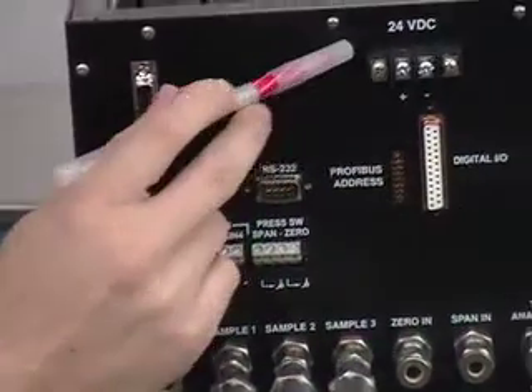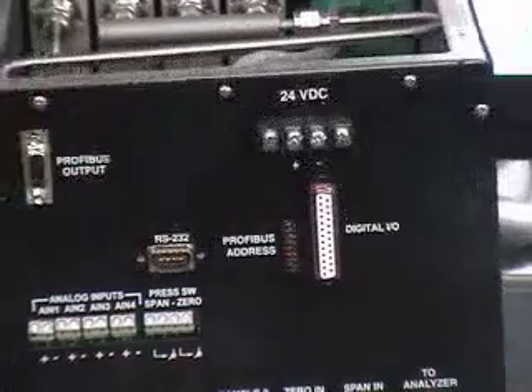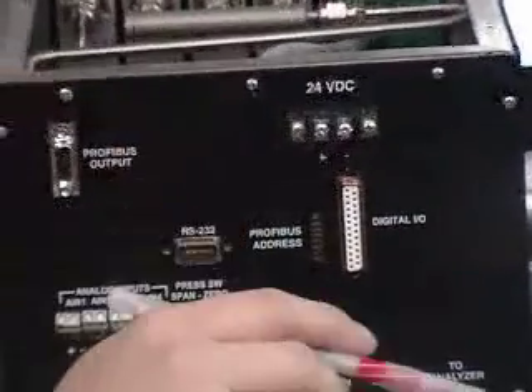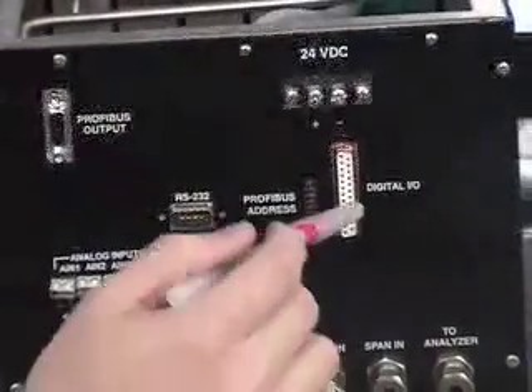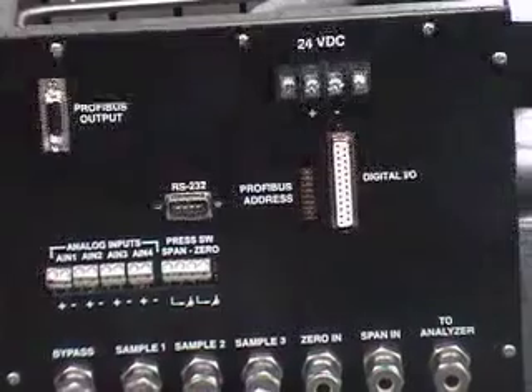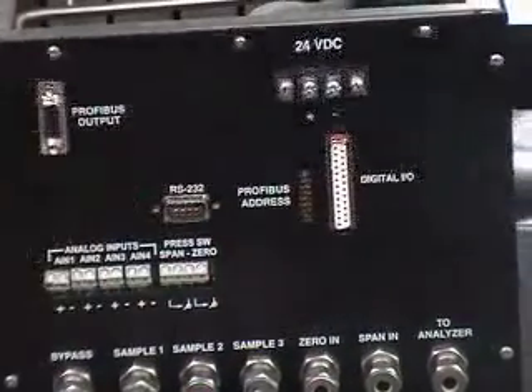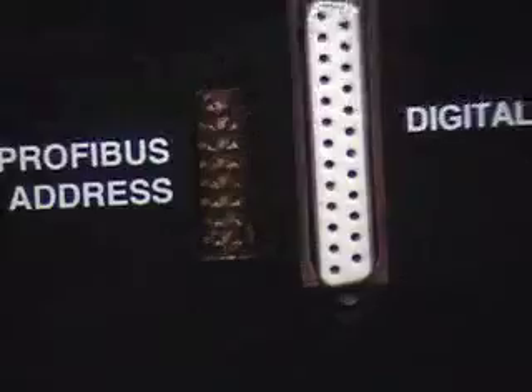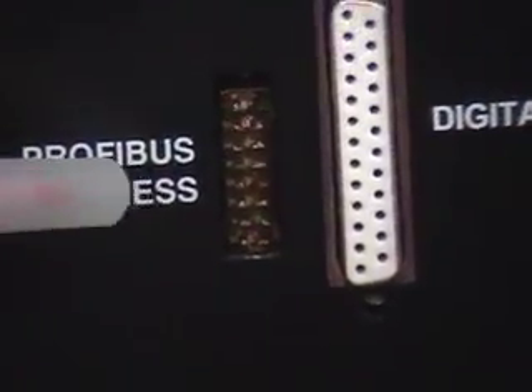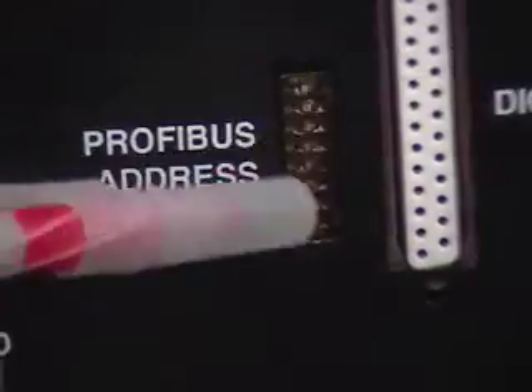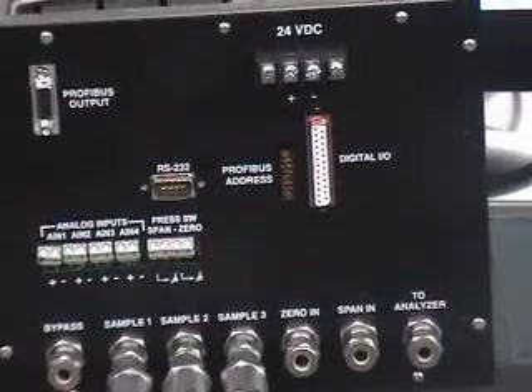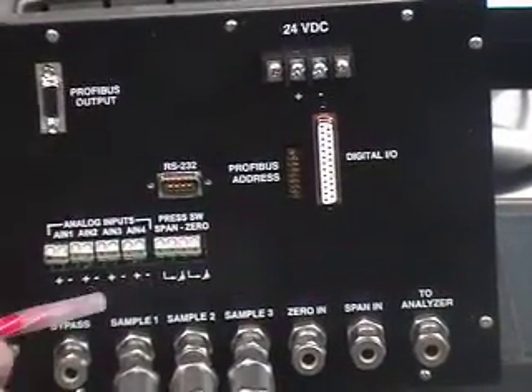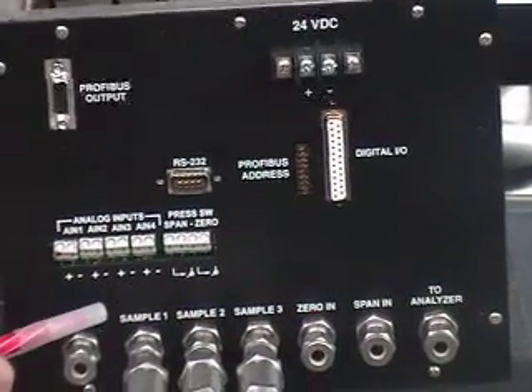This BB1 needs a 24-volt power supply, which we connect over here on this terminal strip. Now, to set it up for the Profibus network, you first need to know what will be the address of the instrument. These dip switches over here on the back will let you set that address. Position number 1 is address 1, all the way to position number 7, which is address 64. In this case, position number 7 is on, so the address of this instrument is 64. When it's connected to a computer or a PLC on the Profibus network, it will communicate with this unit as address 64.